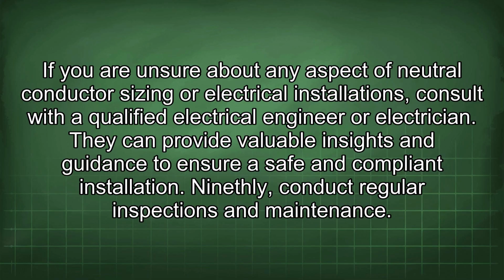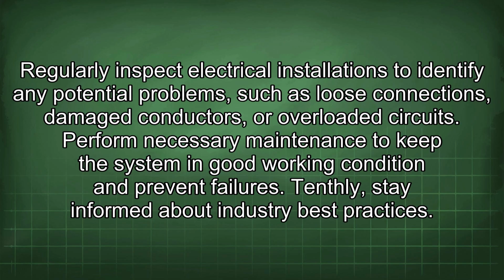Ninthly, conduct regular inspections and maintenance. Regularly inspect electrical installations to identify any potential problems, such as loose connections, damaged conductors, or overloaded circuits. Perform necessary maintenance to keep the system in good working condition and prevent failures.